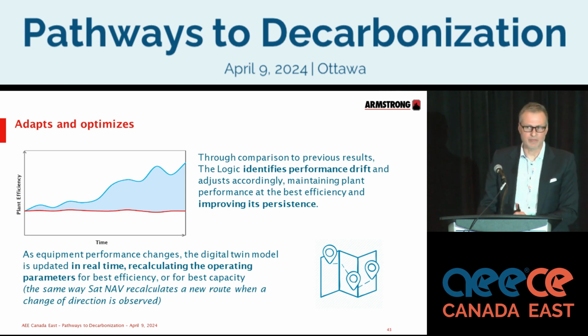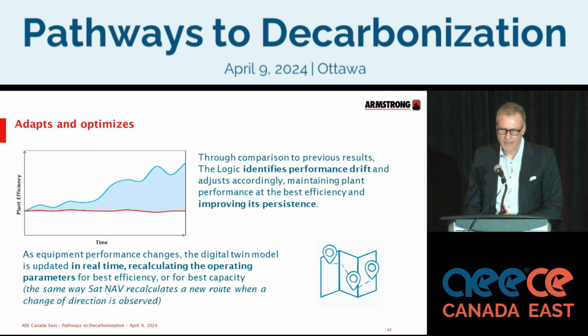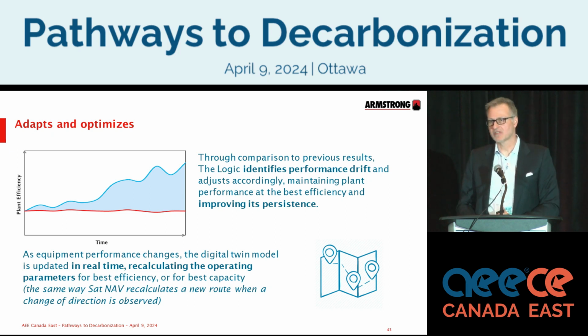There's another case in point where we had a project and we weren't getting the performance that we expected. The long and short of it was that through the analytics, we were able to determine, and this was an 8,000-ton plant, that in one of the chillers, approximately 20% of the evaporator tubes were plugged.